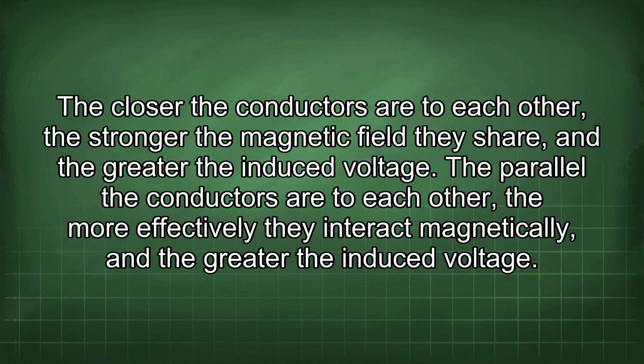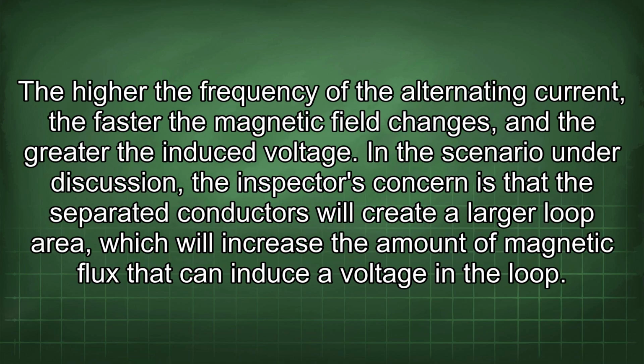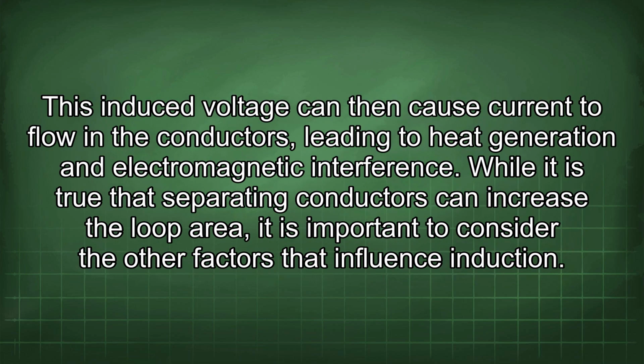The closer the conductors are to each other, the stronger the magnetic field they share and the greater the induced voltage. The more parallel the conductors are to each other, the more effectively they interact magnetically and the greater the induced voltage. The higher the frequency of the alternating current, the faster the magnetic field changes and the greater the induced voltage. In the scenario under discussion, the inspector's concern is that the separated conductors will create a larger loop area, which will increase the amount of magnetic flux that can induce a voltage in the loop. This induced voltage can then cause current to flow in the conductors, leading to heat generation and electromagnetic interference.